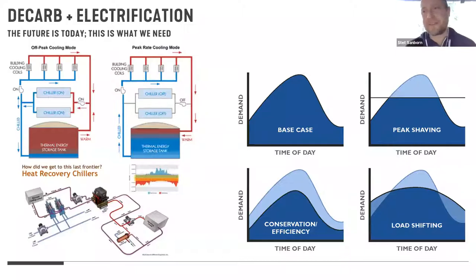The newest utility tariffs came out for California, and there is a huge whopping demand charge for using power between 4 and 9 p.m. And that's precisely because of the graph I showed you earlier, where all the renewables are ramping down and demand goes up while everyone goes home and turns on everything at their house. Our grid is having a challenge, especially in spring, in that 4 to 9 p.m. period. And so the new tariff structure that just came out puts a whopping demand charge on using power then. So all of our clients now are saying, how do I not use energy from 4 to 9 p.m.? Which, if you think about when you see your peak load in the summertime, this is driving huge dollar conversations. And for us, it means thermal energy storage, more so than battery for that particular use.